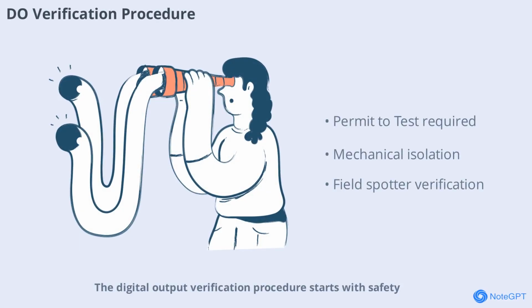Digital output verification procedure starts with safety. You must have a permit to test, ensure mechanical isolation, and use a field spotter to physically verify that the equipment is clear. The control room engineer then forces the DO variable to true in CBM, and the field spotter confirms the device energizes. After verification, the engineer removes the force. This process ensures that outputs are mapped correctly and that safety is never compromised during testing.